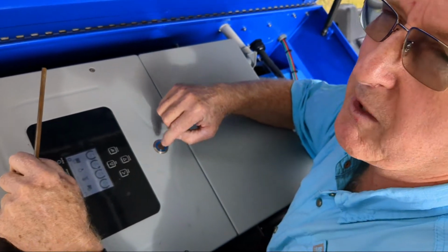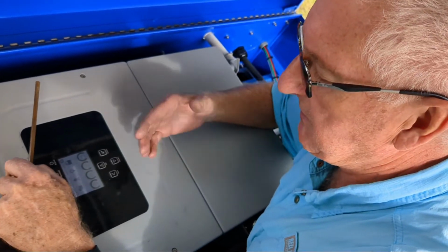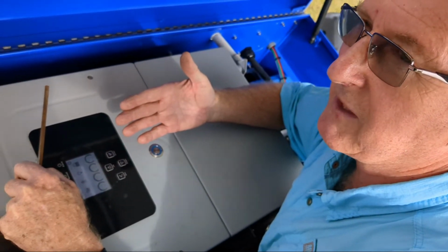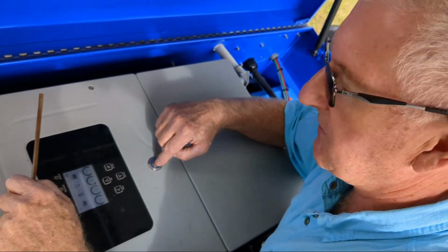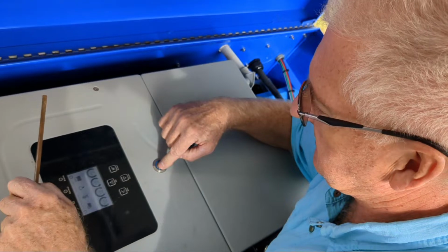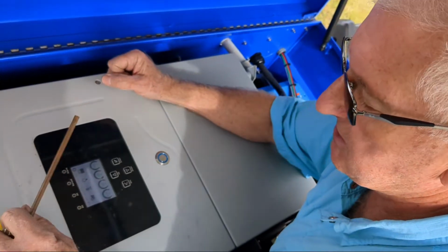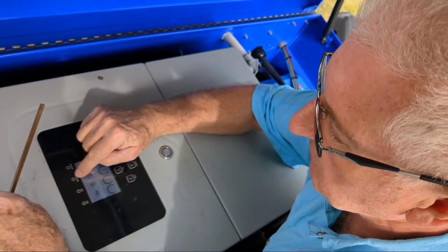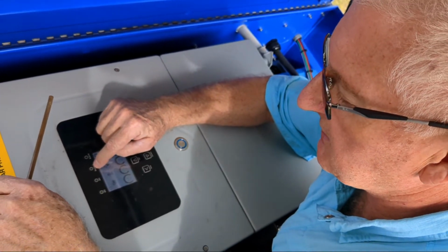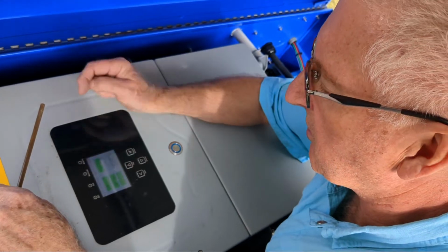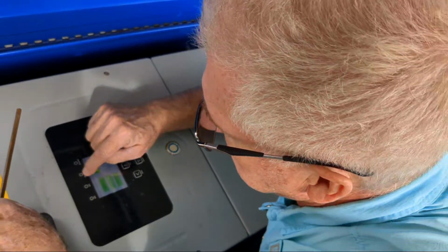But what you don't want to be doing is cycling this all the time, because there's a delay of several minutes for it to start up, you don't know if it's on or off, which is kind of... It should be on now. I did press it, so don't touch it again. Oh, okay. So it'll start up. And what we're looking for before we do anything with an inverter is we want to see it come into normal with no alarm condition. And so this will light up.